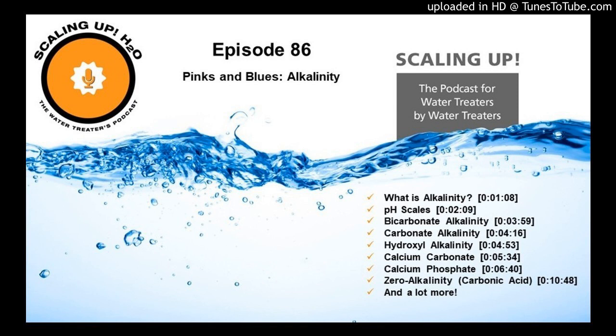So we have bicarbonate alkalinity that exists between 4.3 and 8.3. Between 8.3 and 10.3, we have carbonate alkalinity. And above 10.3, we have hydroxyl alkalinity. And if you can think back to some of your service reports, like boilers, you probably had an OH alkalinity that you had to write down.